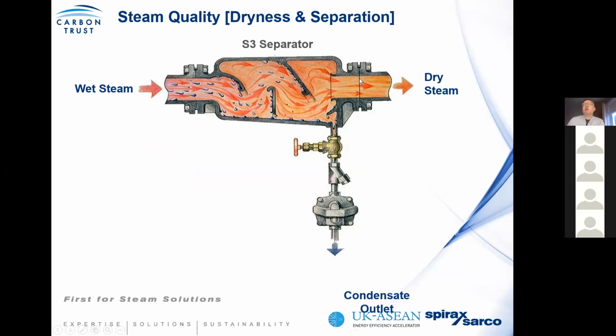What you have then is high quality dry steam to your user, and that higher enthalpy of steam means you have higher energy available to your end user. So, for example, on a kilowatt basis, if you can supply steam at a unity dryness fraction instead of, say, 0.9, you will use nearly 10 to 15% less steam on a kilowatt basis. And it's important to understand that if you have higher quality steam, then your boiler has to do lesser duty, because it's only operating using steam at the highest properties.